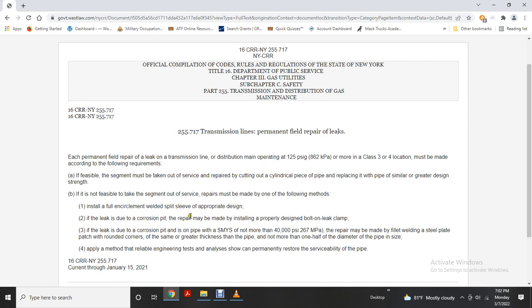If the leak is due to corrosion pitting, the repair must be made by installing a properly designed bolt-on leak clamp. If the leak is due to a corrosion pit on pipe whose specified minimum yield strength is not more than 40,000 psi, the repair may be made by fillet welding a steel plate patch with rounded corners, of the same or greater thickness than the pipe and not more than one half the diameter of the pipe in size. Alternatively, apply a method that reliable engineering tests and analyses show can permanently restore the serviceability of the pipe.